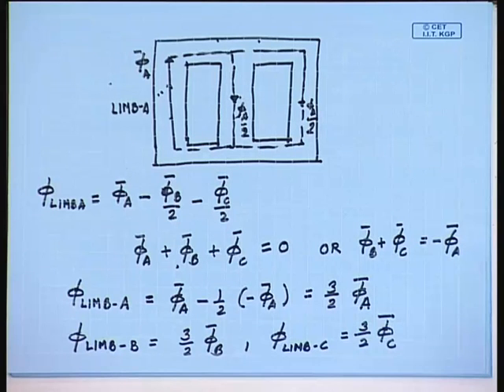Hence, as far as analysis of a 3-phase transformer goes, each phase can be treated separately, at least with balanced applied voltage and in steady state. This makes the analysis of a 3-phase transformer very simple. It can be performed just like a single phase transformer, if we can find out what is the applied voltage across each winding.